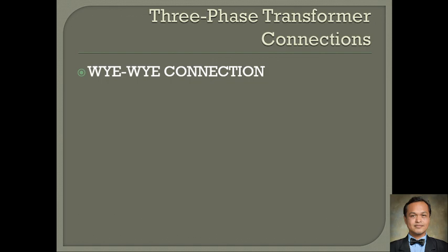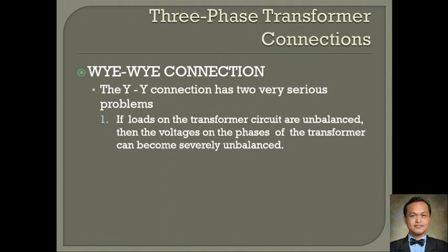Now, the major disadvantage of the Y-to-Y connection is that if you have an unbalanced load, that transformer will suffer severely. It will cause a severe unbalance in the transformer itself. And there is a large presence of third harmonic voltage.